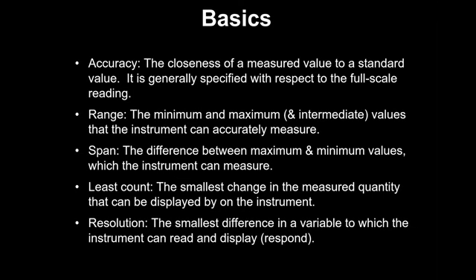So why they were doing a measurement of temperature. Now temperature measurement they were doing with a thermocouple having a range of 0 to 600 degrees centigrade. So I asked them, why are you using this instrument? Because I thought 0 to 600 degree thermocouple is not appropriate for doing such kind of measurement. They said, no, sir, the RTD is occupied somewhere else. So we said, might as well use this instrument. So we using it. Then I asked them, and I asked their company person also, do you know what is the accuracy of this instrument? The accuracy of thermocouple, typically, what instrument they had is 0.25%, which is good.